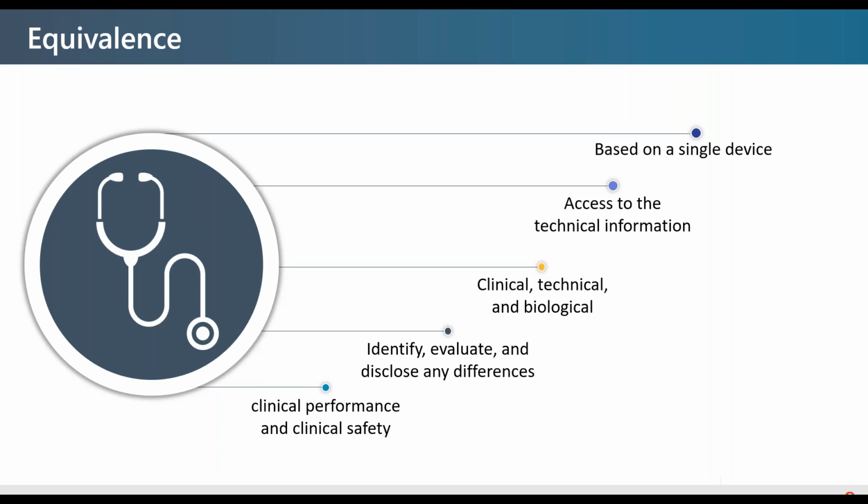You have to show clinical equivalence, so that really means the same indication, intended purpose, and body site with similar population and performance. So same is same, and similar can have some variance, right? And this is kind of a hard one for our engineer people to understand sometimes, but if I have a device that I'm putting in the arm and I want to put it in the vein in the neck, it can't be my equivalent device because it's not the same body site.